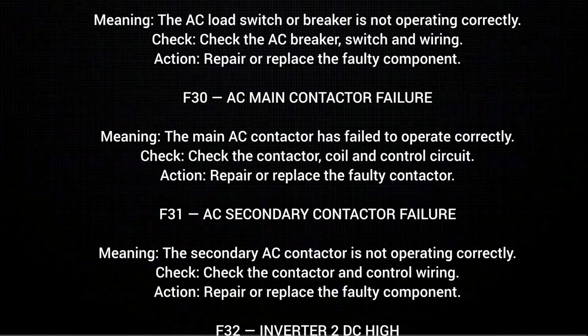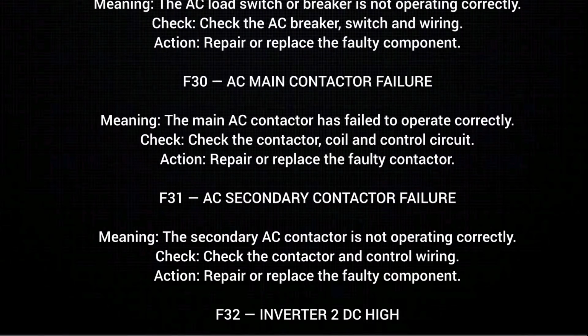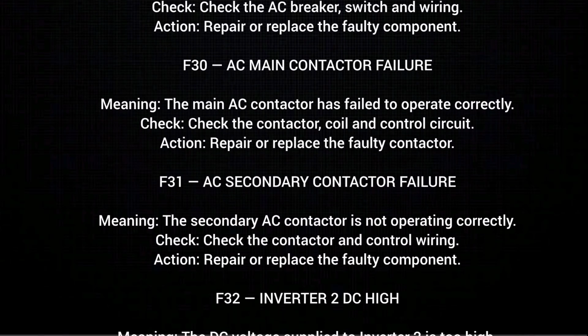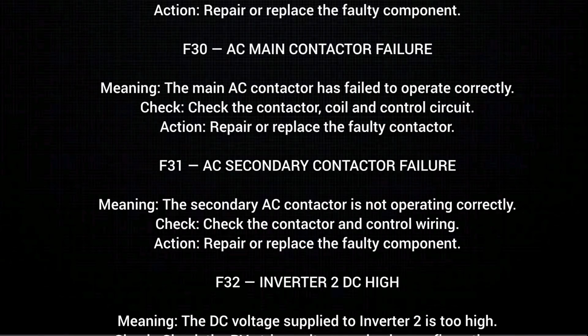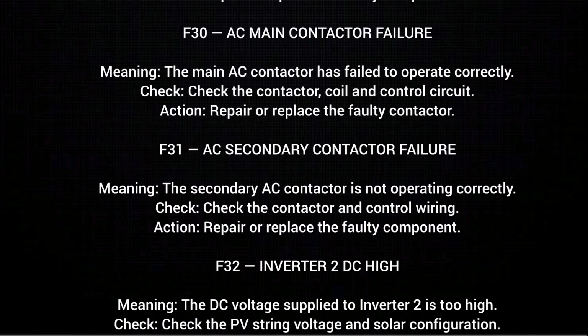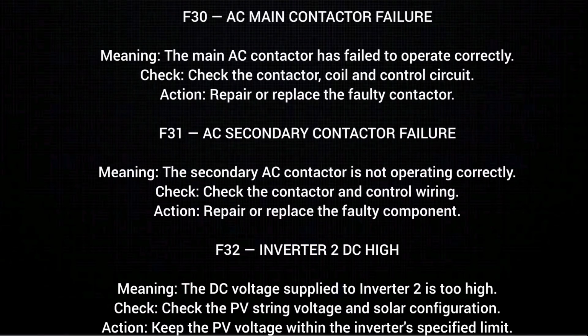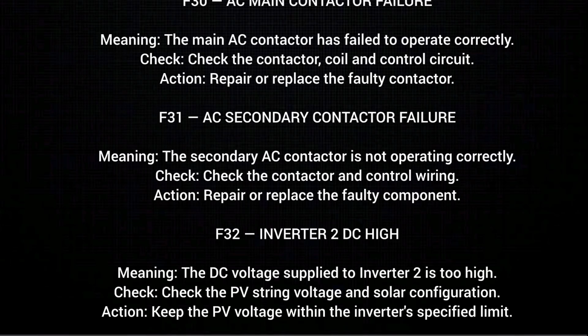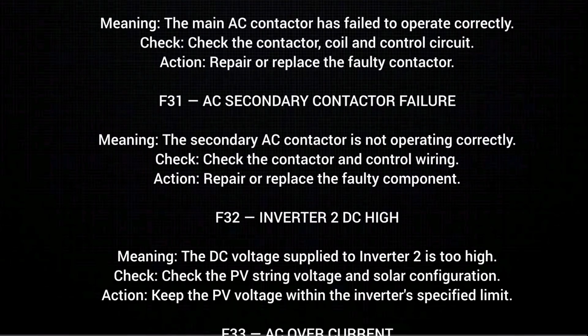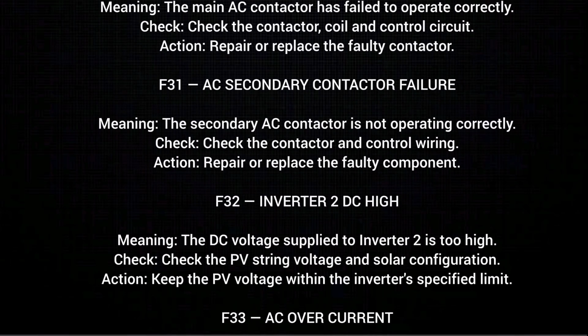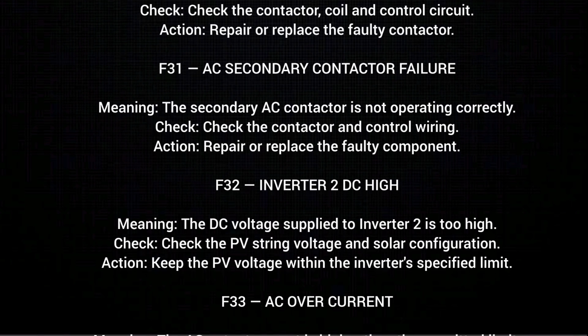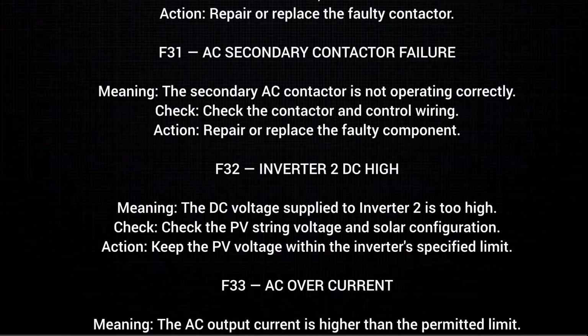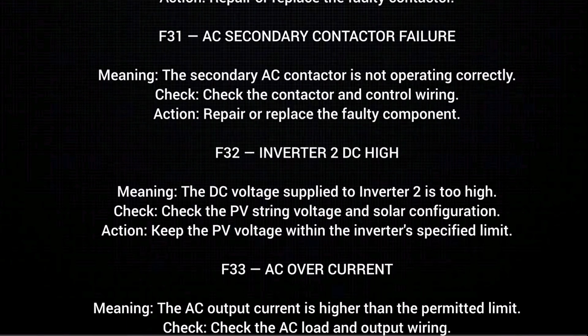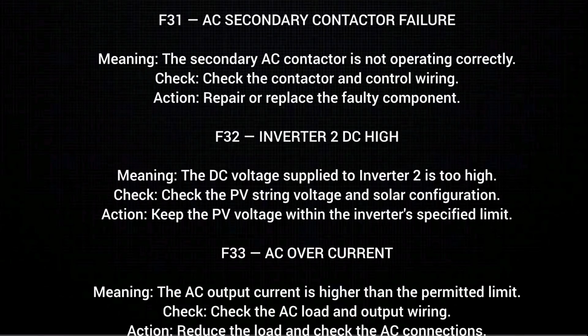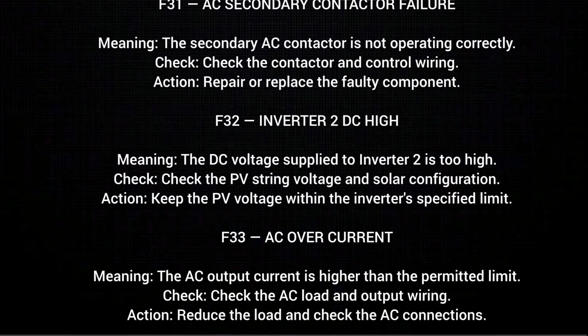F30. AC main contactor failure, meaning the main AC contactor has failed to operate correctly. Check. Check the contactor, coil and control circuit. Action. Repair or replace the faulty contactor. F31. AC secondary contactor failure, meaning the secondary AC contactor is not operating correctly. Check. Check the contactor and control wiring. Action. Repair or replace the faulty component.